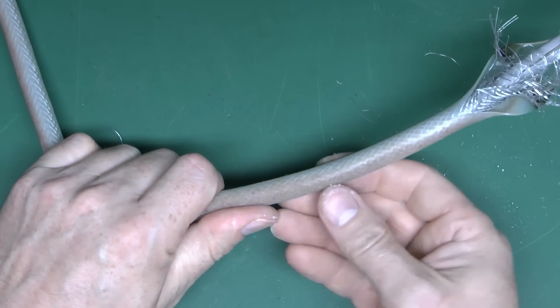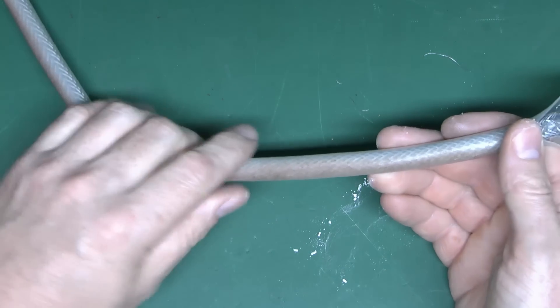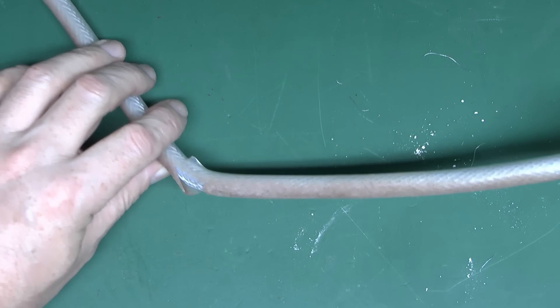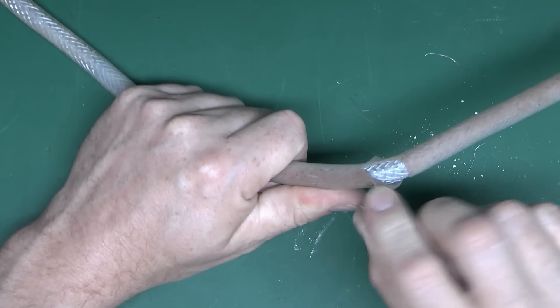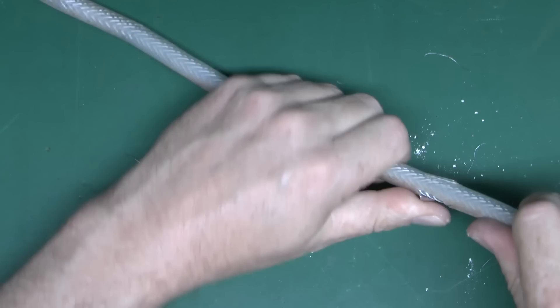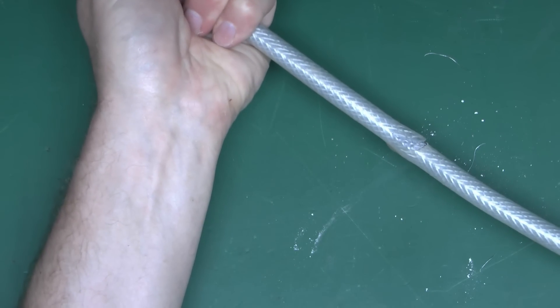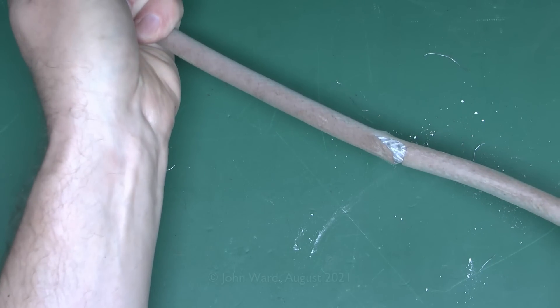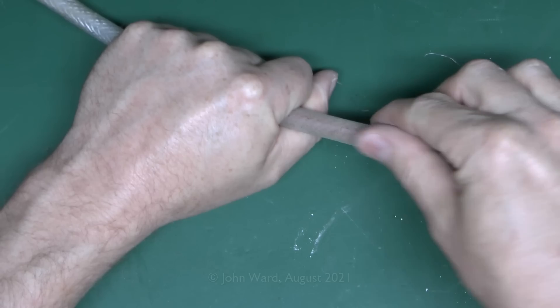The other problem with this stuff is that this outer covering is not UV resistant, unlike generally black cables are. So what will happen is that if this is exposed to the sunlight and the weather, you get things like this, where the outer covering has just deteriorated away, cracks apart, and starts to disintegrate. You can see on this that this side of it looks perfectly reasonable. You turn it over, and it's all discoloured and brown, because that's where the sun has basically damaged the outer covering.